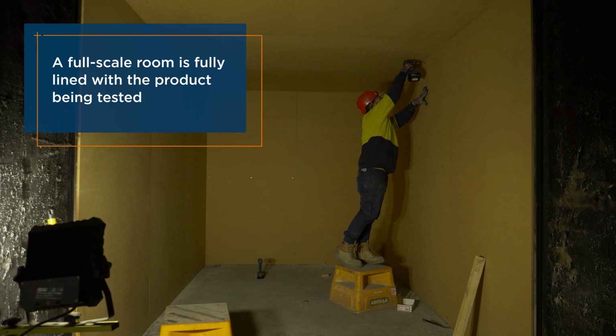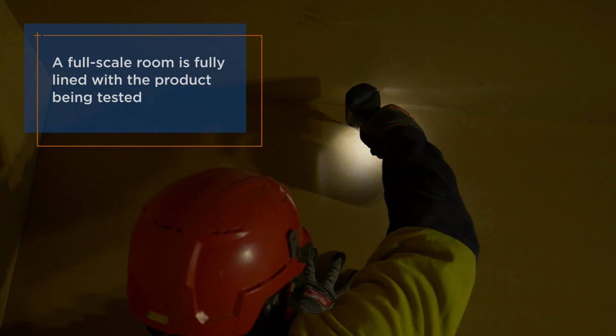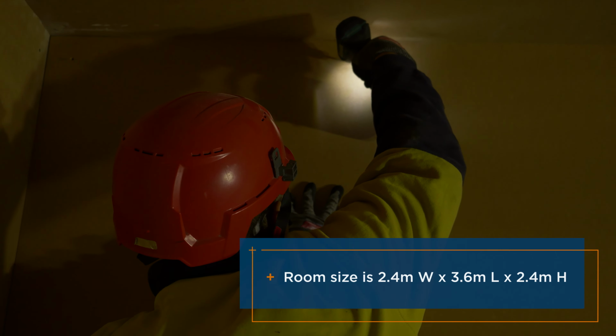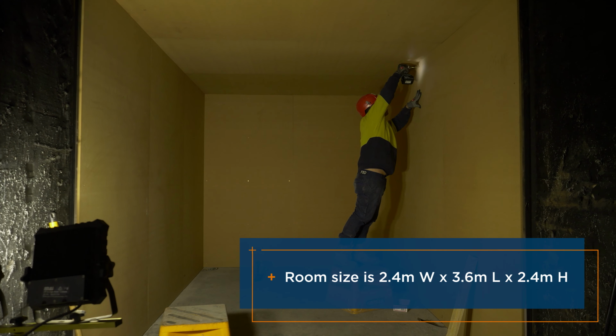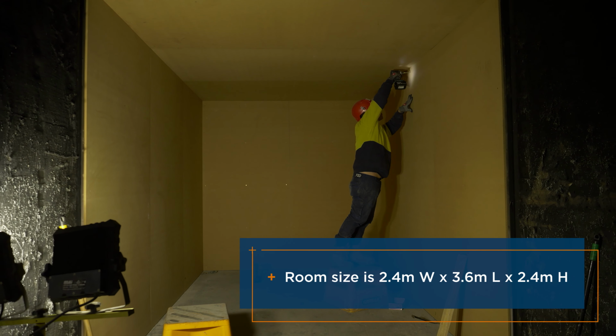The test method is intended to evaluate the contribution to fire growth provided by a lining product or assembly using a specified ignition source. As the name suggests, a full-scale room with non-combustible internal surfaces is lined with the product being evaluated. Three walls and the entire ceiling must be covered. The room size is 2.4 metres wide, 3.6 metres long, and with a ceiling height of 2.4 metres.